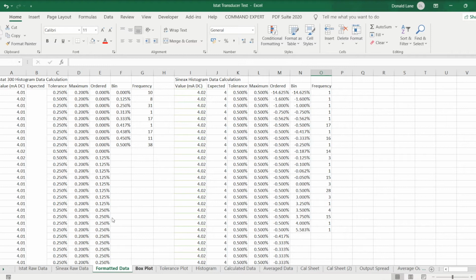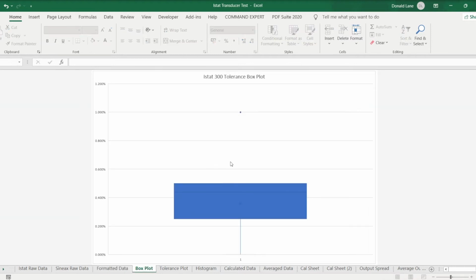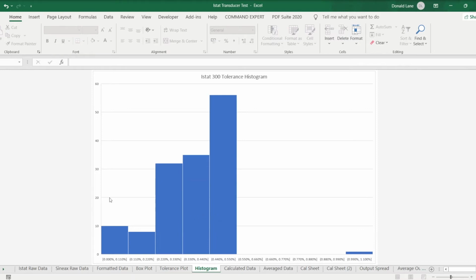First is the box plot, and you can see here this is the bulk of the readings with regard to the tolerance in there, but you can also see up here there's a reading at 1%, which starts to look like an outlier to me. I can look at that a little bit better. If I look at the histogram over here, again you see the bulk of the readings are down here at this 0% tolerance to 0.5%, and you've got this reading up here on its own, sitting well and truly away from the bulk of the readings.